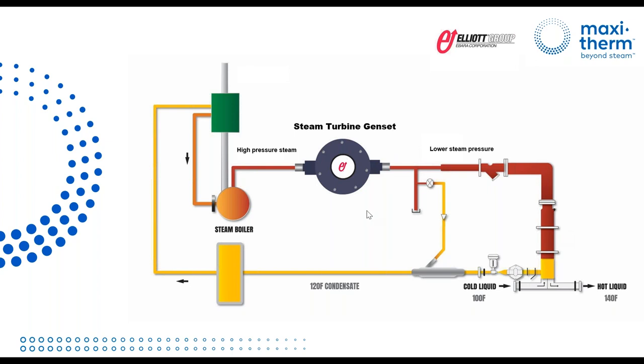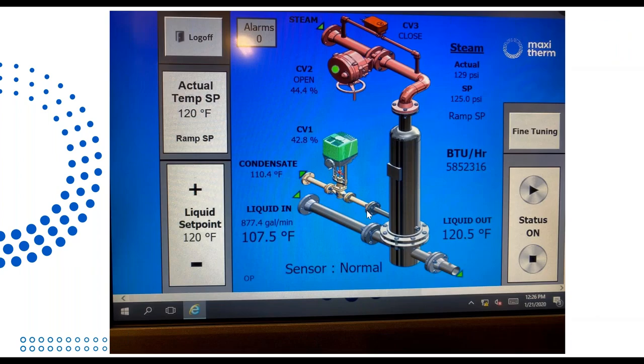Hold on, I don't know why we're not switching. Here we go. So the way it works, there's only one moving part. This is the main moving part, the control valve, which is on the condensate. When the valve is modulating based on your set point, the condensate level moves up and down in the heat exchanger with no water hammer, no nothing. Those valves at the inlet are on-off devices for startup or shutdown purposes. But otherwise, the only moving part is the control valve here.